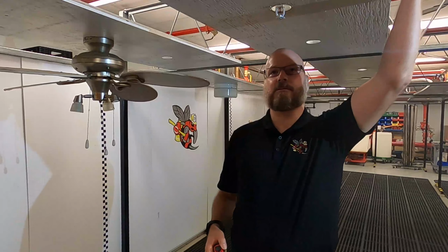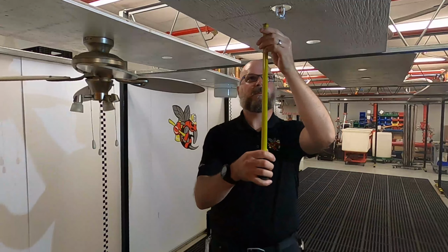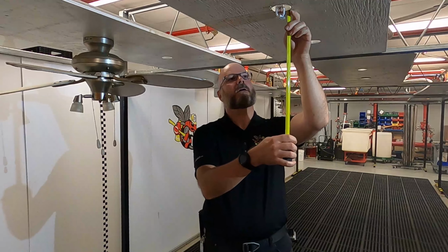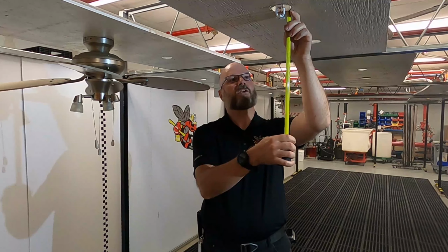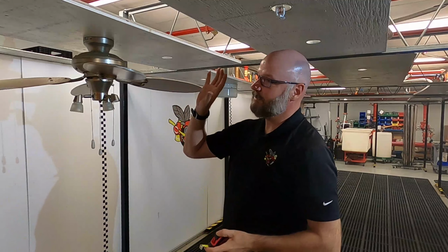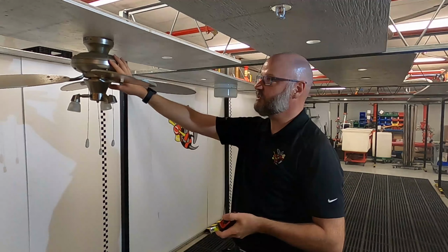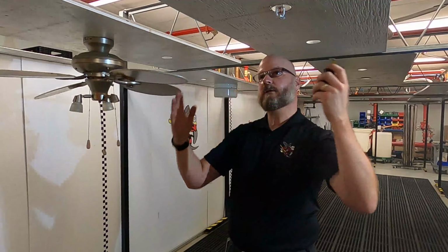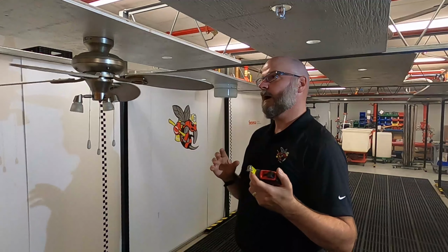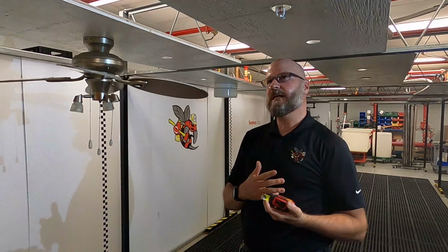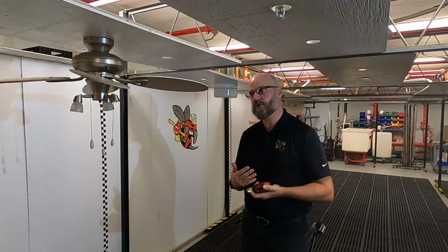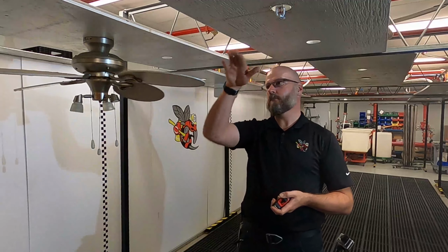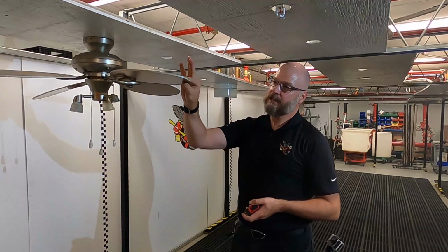When we think about the sequence of what we need to do, we're really looking to determine the deflector distance down from the ceiling, which we're going to say is approximately 1 inch right now. We also, when we think about our obstructions, this one's a little bit more challenging because it's a ceiling fan. With ceiling fans and the sprinkler head spray patterns, the first thing that water is going to hit has normally been my rule for where we measure from.